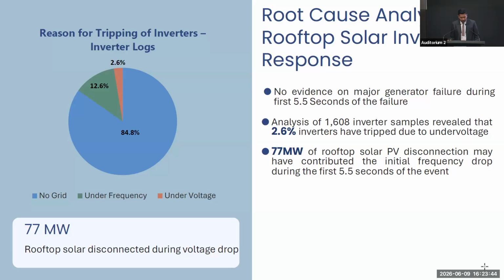Therefore, the rooftop solar inverter data collected by the utility was analyzed by the commission in order to understand the behavior of the rooftop solar during this failure. Through the analysis of the tripping logs of 1,608 inverter samples, it was found that the majority of the inverters recorded a no grid situation. That means most of the inverters tripped off due to the no grid situation. And we found that 2.6% of the inverters tripped due to under voltage, which happened during the first 1.1 seconds of the failure. Then, based on the analysis of rooftop solar PV capacities connected to the nearby affected grid substation, we found that approximately 77 megawatts of solar generation would have gone out from the system, which could have led to the frequency drop during the first 5.5 seconds.